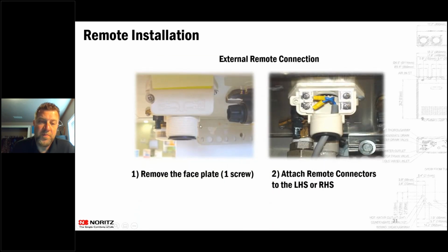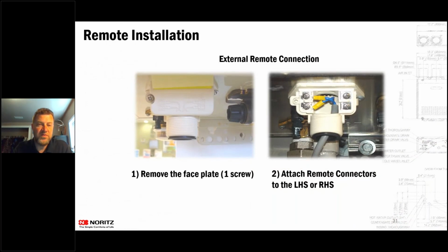On the bottom of the units, you'll see this remote control terminal. You just remove this one screw, pull it off, pull the two leads up there, and put the alligator clips on either the left side or the right side. You just pick a side and put it through there. Different manufacturers have different ways that you hook those external remotes up. Some are up inside of the unit, where it clicks together, or you put it together in many different ways. But if you are using an external remote, typically it's going to be this type of fashion. Before we move on to combustion air, any questions on remote controls?